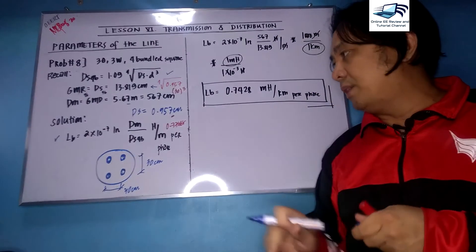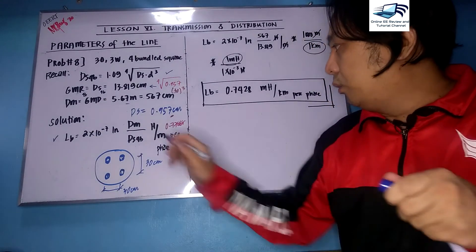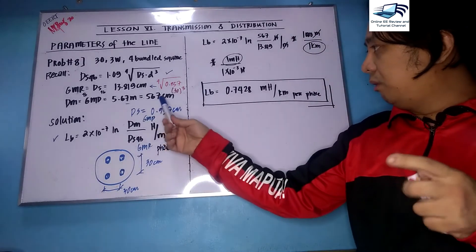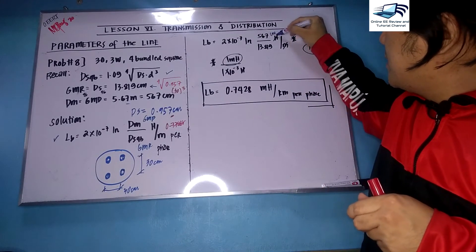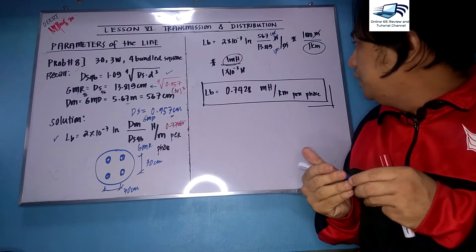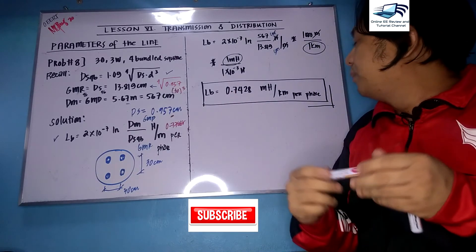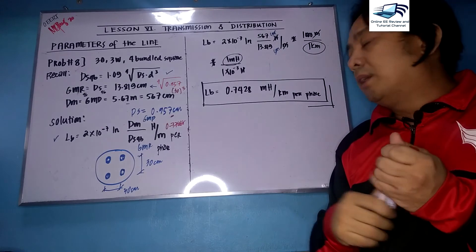We can now solve for inductance of the bundle configuration using the classical formula: L equals 2 times 10⁻⁷ times ln(Dm / DS) henry per meter per phase. Substituting: 2 × 10⁻⁷ times ln(567 / 13.819) — the centimeter units cancel out. Converting to millihenry per kilometer by multiplying by 1000 meters per kilometer and 1 millihenry per 10⁻³ henry, the result is 0.7428 millihenry per kilometer per phase.